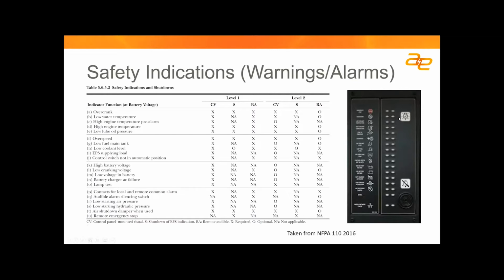This picture on the right, hard to see, is a standard remote annunciator panel, this one associated with Caterpillar. You can see symbols for the different types of alarms, and a row of LEDs — typically yellow LEDs for warnings, and a red LED for anything that's a shutdown alarm. There's also a siren, a silence button, and a lamp test. That's typical for most hospitals; you're probably going to see something similar.